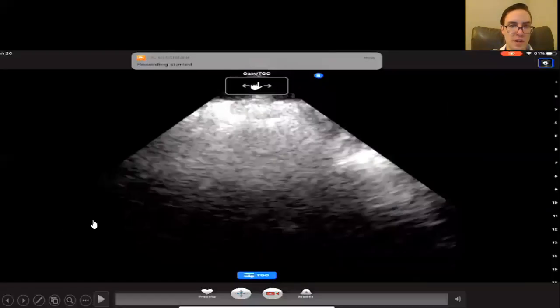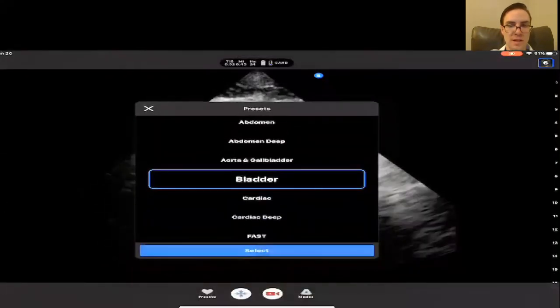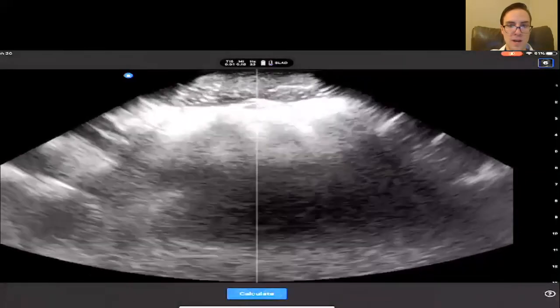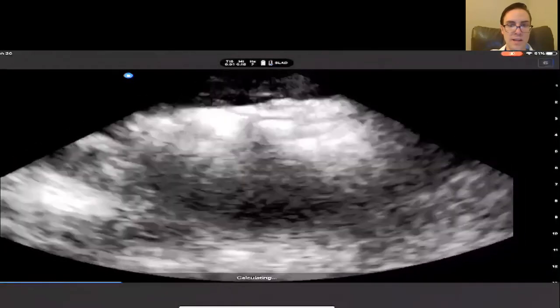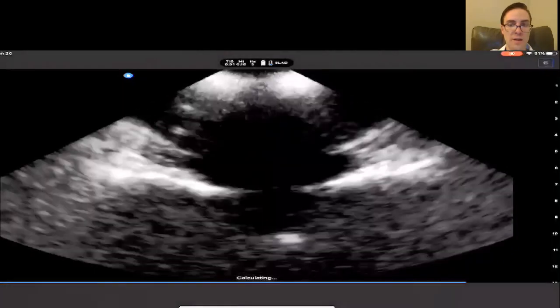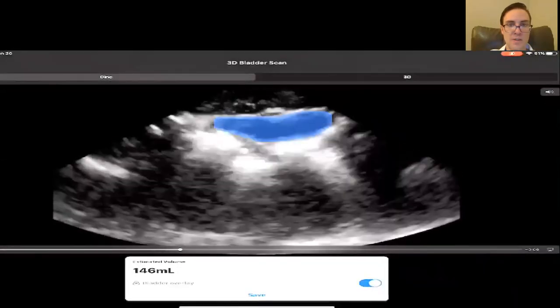This video puts it all together. First I'm selecting the bladder preset, then the volume icon at the bottom, and now it's calculating. You can see that little blue area — that's it identifying the bladder. I click calculate, it's running through, and I'm scanning the entire bladder while it's doing this. I went through the entire section and now it's showing me its work.